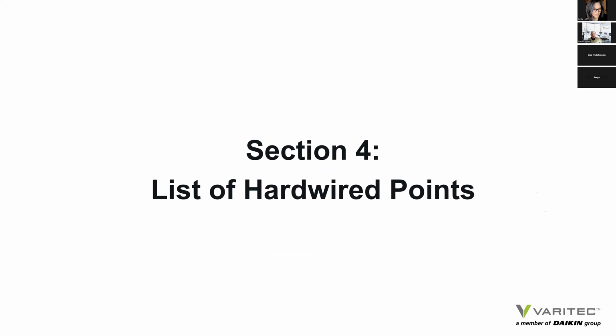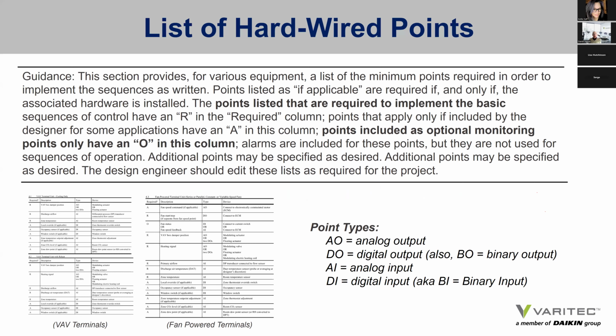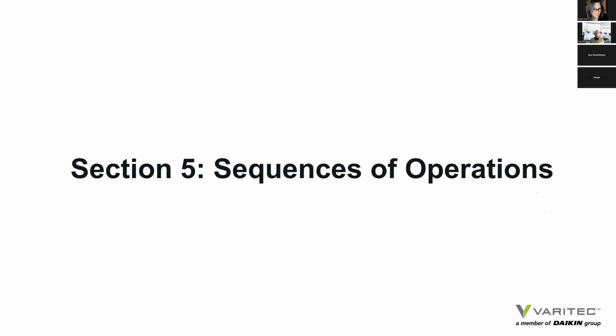In order for all of these set points to be properly communicated and controlled through the BAS, the guideline offers a list of hardwire points for all the types of VAV devices that are available, and that actually writes out what points are listed as required, what points are actually to be included by the design team for applications as an A in the column. Points included as optional monitoring points shall have O values, etc. So it offers direction in the hardware list of how these actual points are to be dealt with within the actual controls platform. And then there's section 5, the actual sequences of operation.